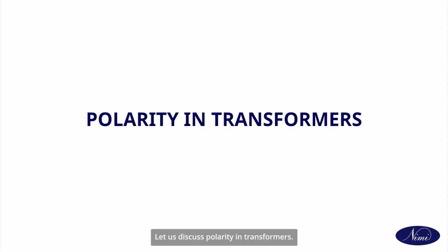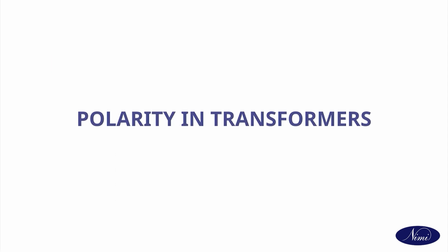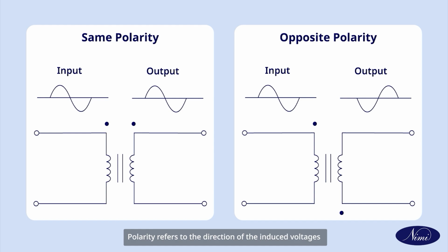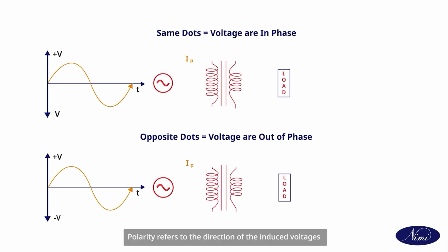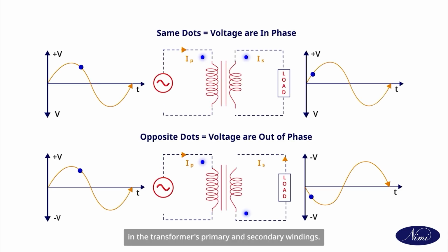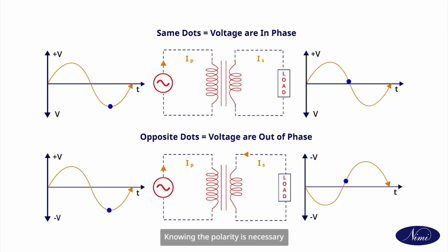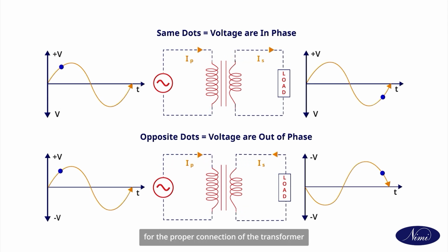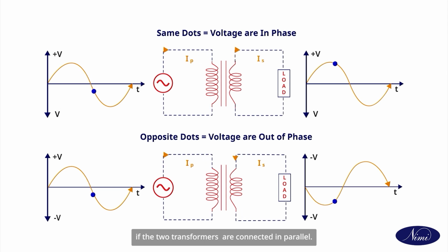Let us discuss polarity in transformers. Polarity refers to the direction of the induced voltages in the transformer's primary and secondary windings. Knowing the polarity is necessary for the proper connection of the transformer if the two transformers are connected in parallel.